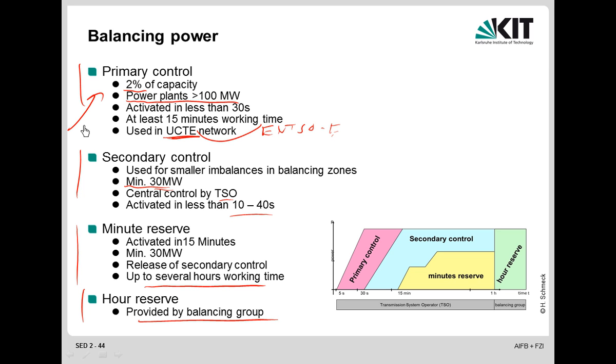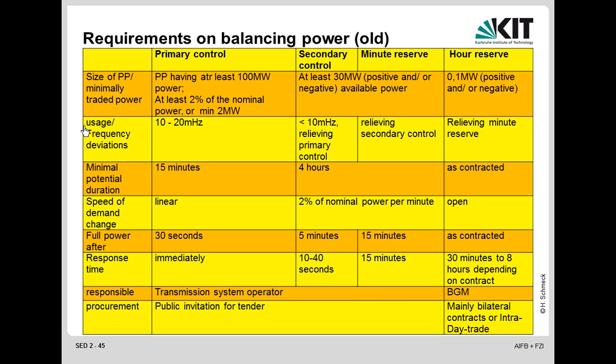If you have smaller devices, there is a certain demand for the complete power that you need in order to stabilize the frequency. For Germany, that is in the range of 500 megawatt that you must have under contract in order to provide the needed primary control power. And they didn't want to have too many contractors for that. They didn't want to have too many devices, so they just said we only want the large power plants. They can do that in a very stable way. And now these things have changed, and the requirements for the provisioning of primary control power are going down. Okay, I will show you the new things there.